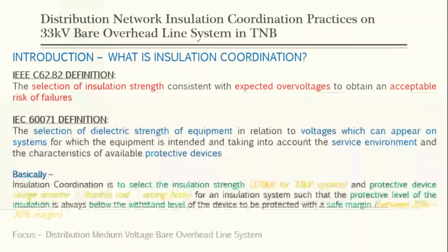Okay, ladies and gentlemen, what is insulation coordination? All right. A definition by IEEE says that insulation coordination is the selection of insulation strength consistent with expected overvoltages to obtain an acceptable risk of failures. And we also have IEC 60071's definition: the selection of dielectric strength of equipment in relation to voltages which can appear on systems for which the equipment is intended, and taking into account the service environment and the characteristics of available protective devices. So basically, ladies and gentlemen, insulation coordination is to select the insulation strength.